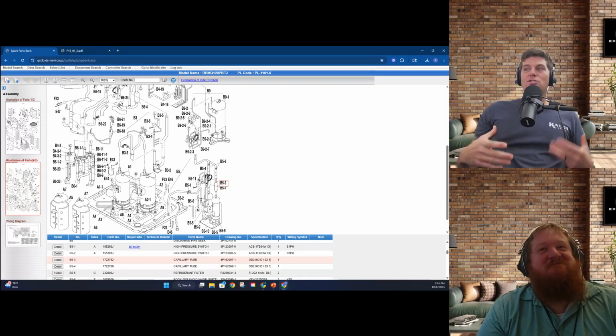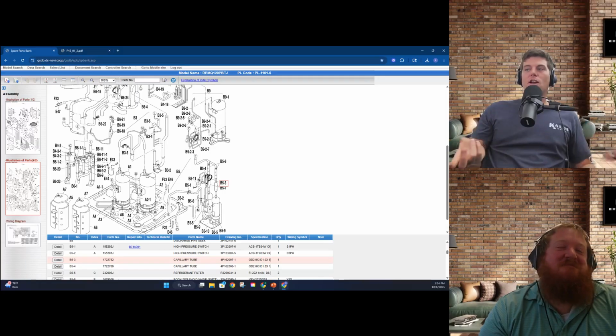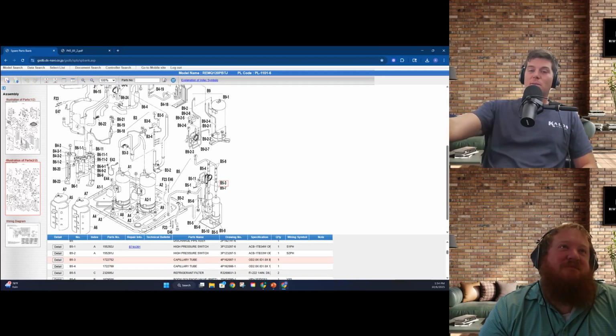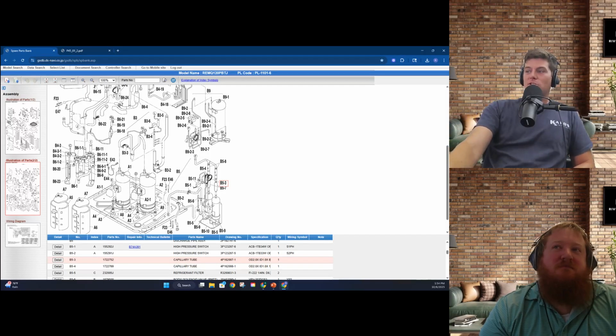And that excessive vibration travels what? It travels up to the suction line, up to the discharge line. Everywhere. The discharge line goes straight to the oil refrigerant separator, so there's no vibration to be absorbed. It goes down to the base. It's got its own mounting bracket on the back of the refrigerant oil separator to hold it in place. But if you look at the capillary tubes on the suction line for the oil return, there's nothing holding that thing in place.